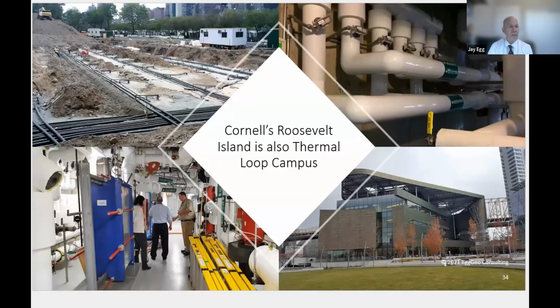As you look at some of these, this is the Cornell campus in New York City. They are using shallow, median temperature thermal energy to provide heat in the winter and cooling in the summer through a set of heat pumps down in this mechanical room that exchange heat with the shallow earth, as you can see right outside. And that thermal energy exchange takes place under this lawn just outside of the Cornell Bloomberg campus in New York City, and runs that energy through these pipes.